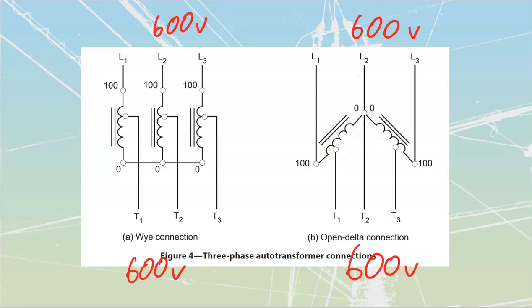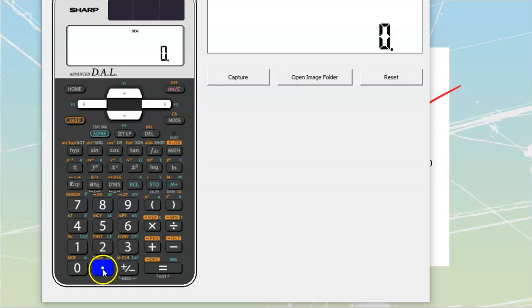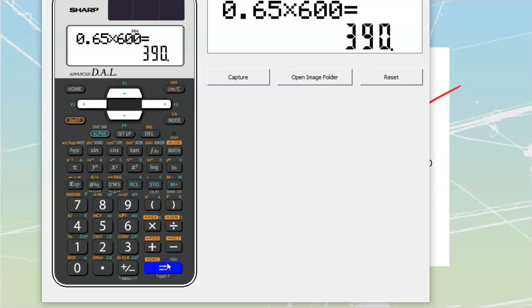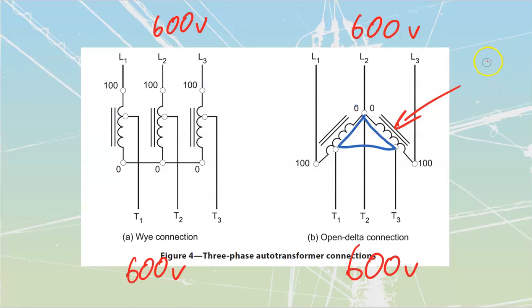When I'm looking at this connection over here, my open delta connection, whatever tap I'm at on those transformers, going from the 0 up, is going to be the percentage of voltage that I'm going to have across there. So if I have a 65% tap, right now I would get 65% of that 600 volts. Let's pull this calculator up here. 0.65 times 600, which would mean that I would be starting this thing up at 390 volts initially to start this motor up.